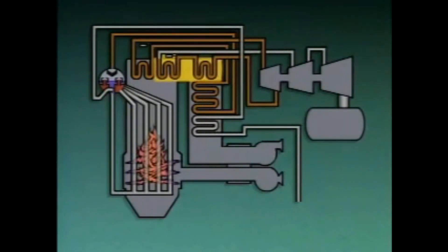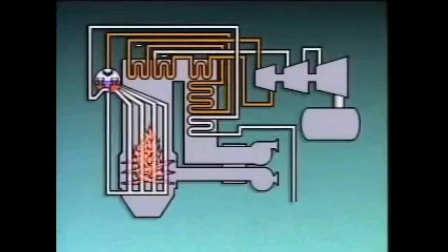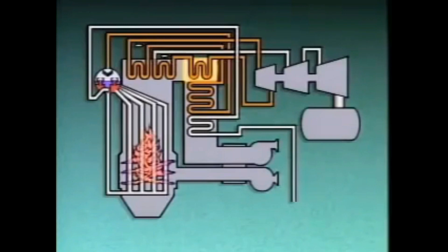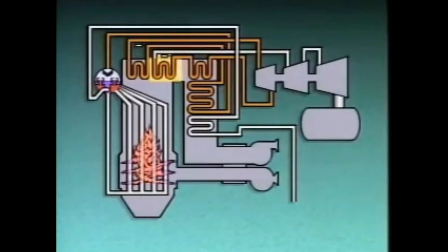Reheaters are very similar to superheaters. They use heat from the boiler furnace or from hot combustion gases to raise the temperature of the steam. For example, this boiler has a primary reheater that the steam enters first as it comes from the high-pressure section of the turbine. After the steam flows through the primary reheater, it moves on to a secondary reheater.